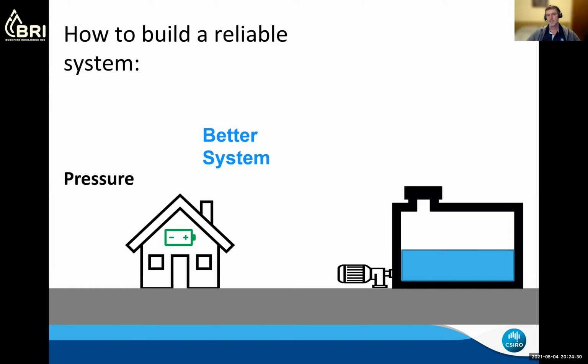So what's a better system than the typical one? Why not electric? Electric pumps can be far more tolerant, handling much higher temperatures, and can be mounted in situ or remotely from the tank. But you've taken the internal combustion engine off the pump and replaced it with an electric motor - so how are you going to reliably provide electricity to that motor?